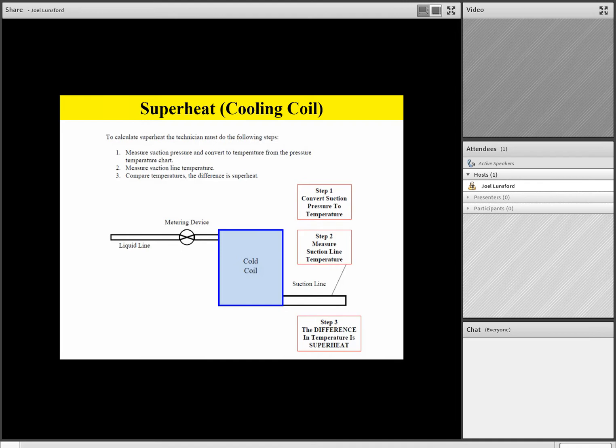If the superheat is high on the cold coil, that coil is starved. If the superheat is low on the cold coil, that coil is flooded. Normal superheat on a cold coil should run about 10 to 15 degrees in the cooling mode, and as low as 4 degrees to 15 degrees in the heating mode. And again, just double check: if the superheat is high, the cold coil is starved. If the superheat is low, the coil is flooded. And if the superheat is normal, it'll fall within that range of about 10 to 15 for cooling mode, and about 4 to 15 degrees for heating mode.